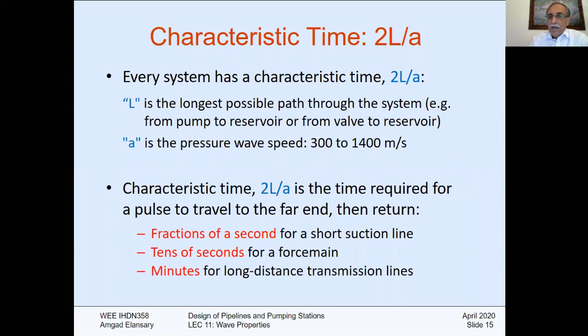For example, if I initiate the valve closure, the closure time with respect to the characteristic time, what will be the ratio between them? Is it larger, smaller, very large? This is what we call the system response to change. Compare it to 2L over A, for example, for valve movement or pump operation.